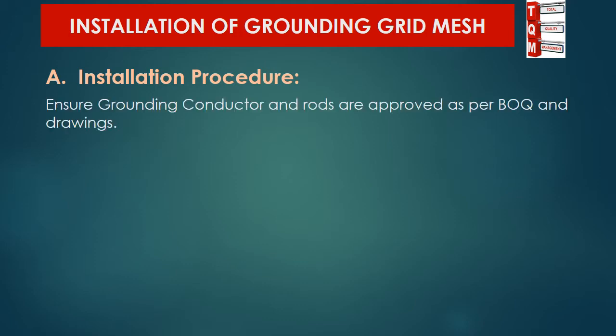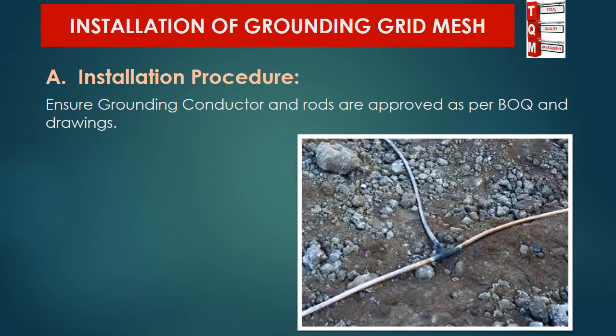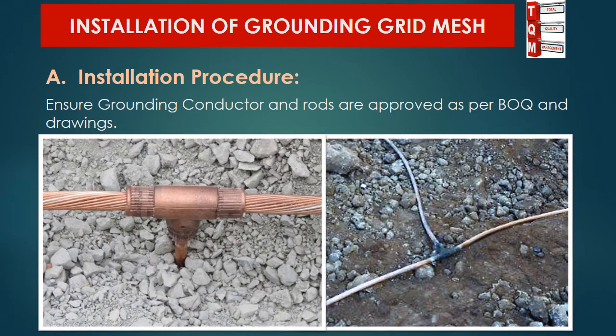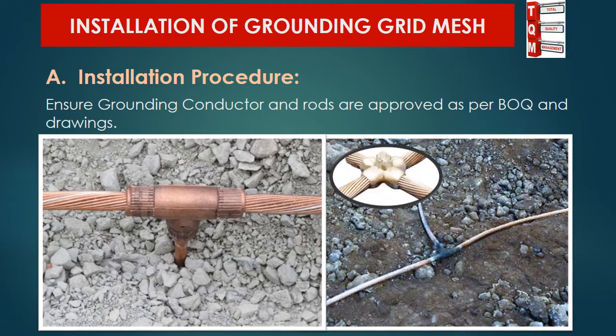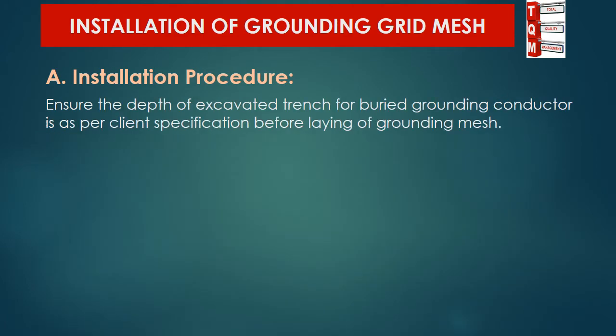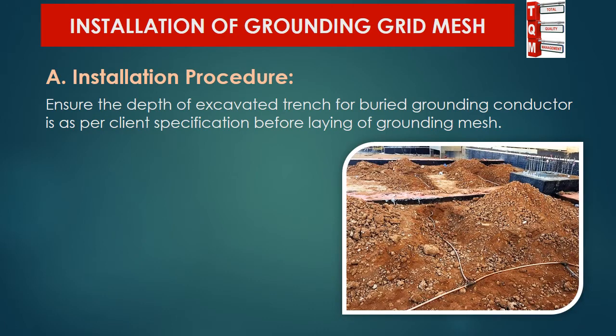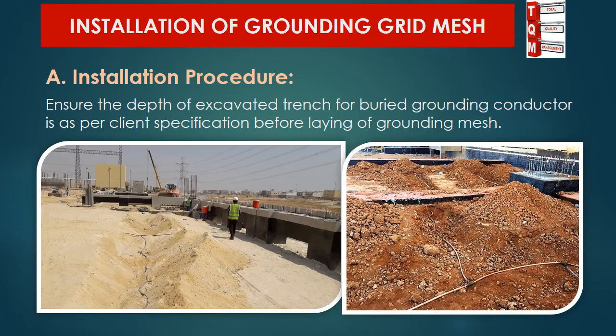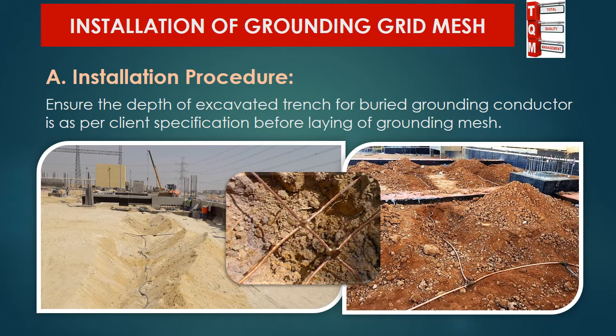The following steps are to be followed for the installation procedure. First, ensure grounding conductors and rods are approved as per BOQ and drawings prior to use at site. It is important to ensure the depth of the grounding conductor is as per client specification before laying — it usually varies from 0.5 meter to 1.5 meter depth from finish floor level. Confirm this depth from approved IFC drawings and lay the mesh at the required level.